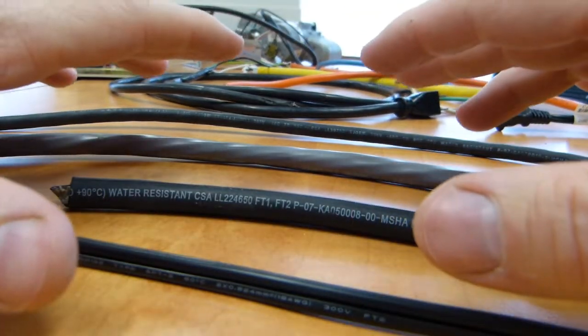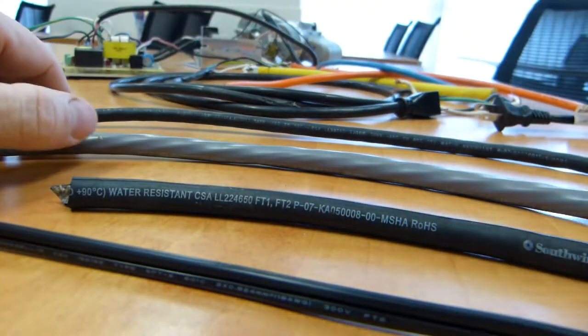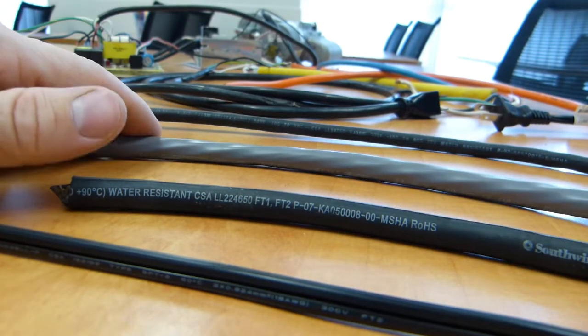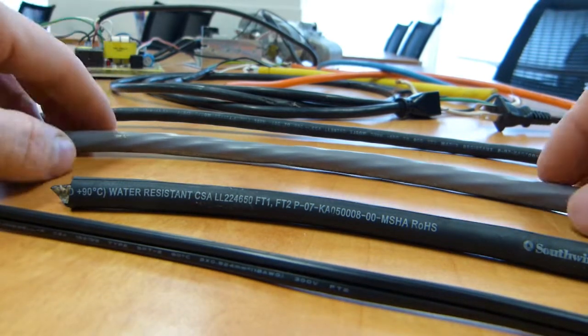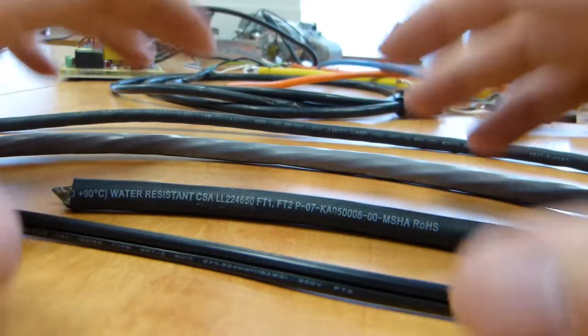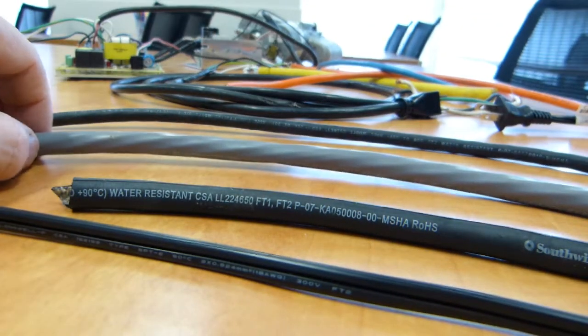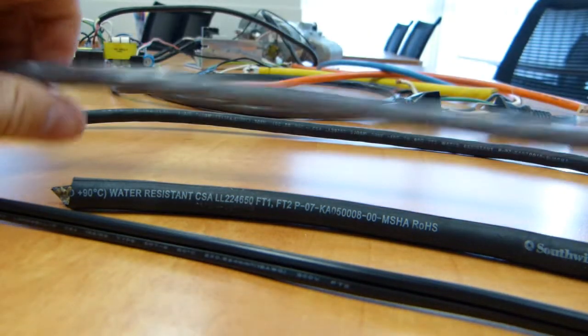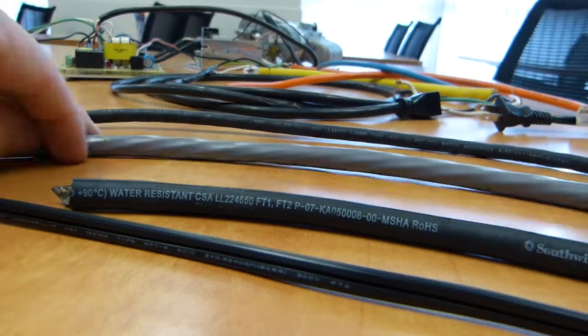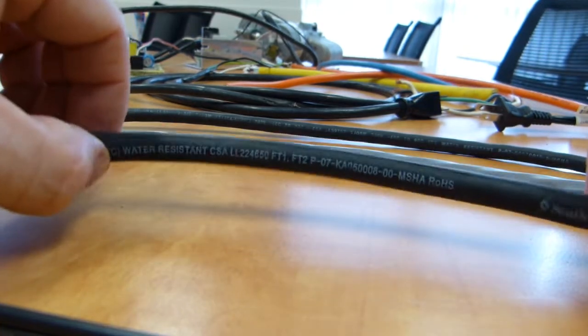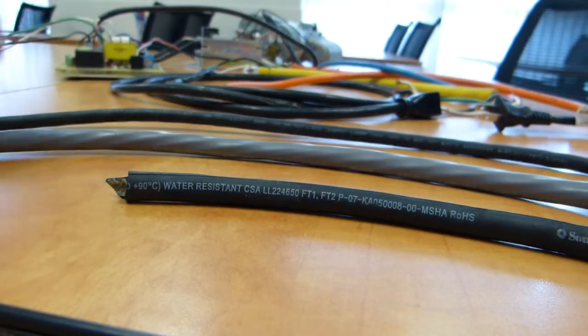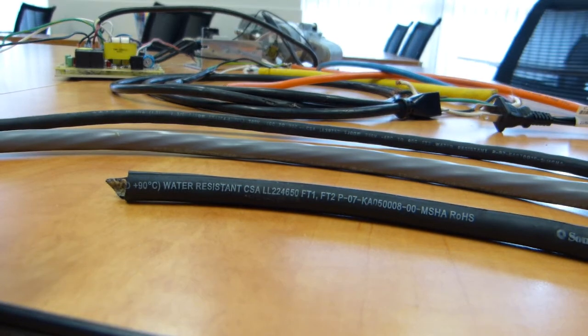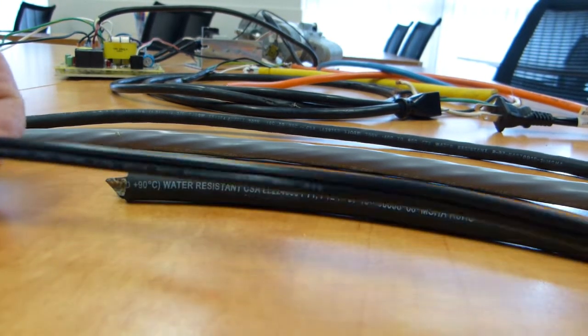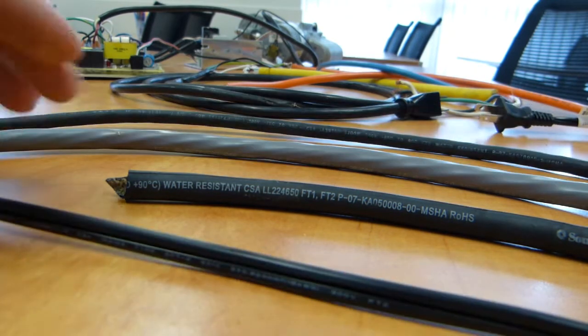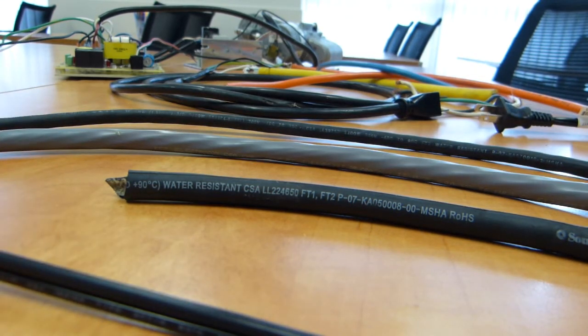...that has hot air circulating in it, say at the source 90 degree hot air? Can you put an extension cord on sheet metal ductwork with 90 degree hot air circulating in it regularly? Yeah, you can try it with this 105 degree cable, and you can try it with this 90-degree cable or this other 90-degree cable. But with the 90-degree cable you're pushing it since you're at the maximum - but absolutely not with the 60-degree or 75-degree cable.